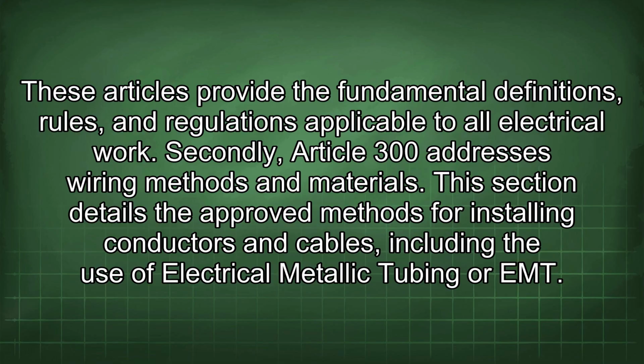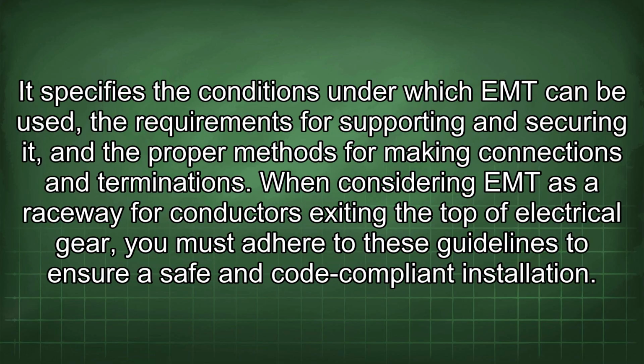Secondly, Article 300 addresses wiring methods and materials. This section details the approved methods for installing conductors and cables, including the use of electrical metallic tubing or EMT. It specifies the conditions under which EMT can be used, the requirements for supporting and securing it, and the proper methods for making connections and terminations.